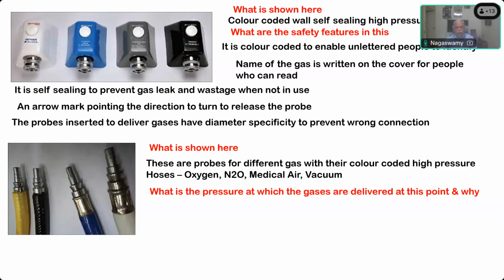Does it go directly to the flow meter, this 50 to 60 psi? If it goes directly to the flow meter, it will get damaged, because flow meters are not designed to face 50 to 60 psi. They can face only 14 to 15 psi. There is a pressure regulator or reducer.